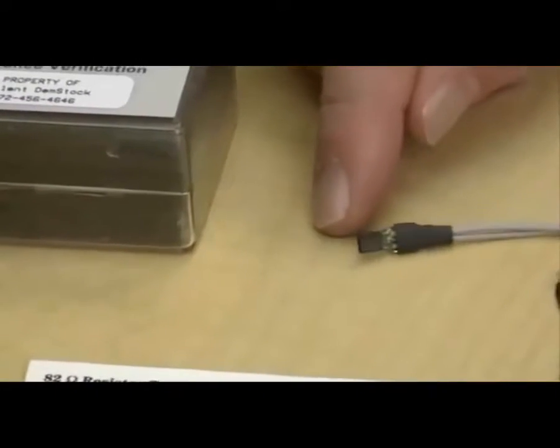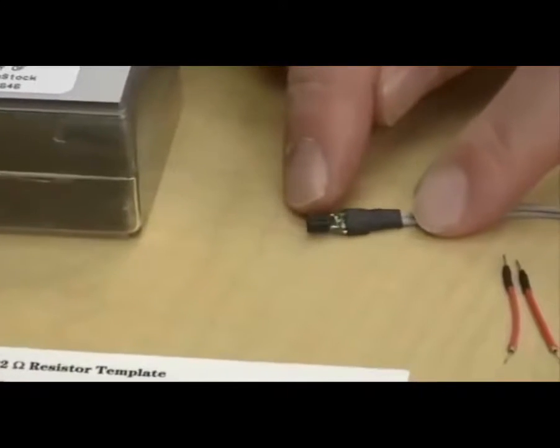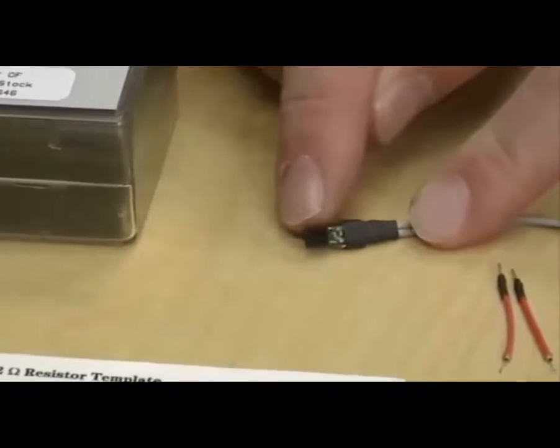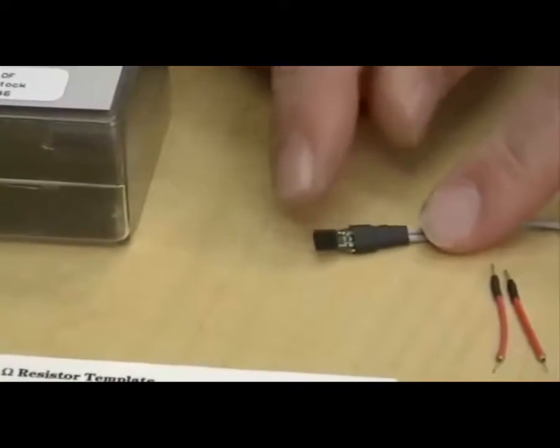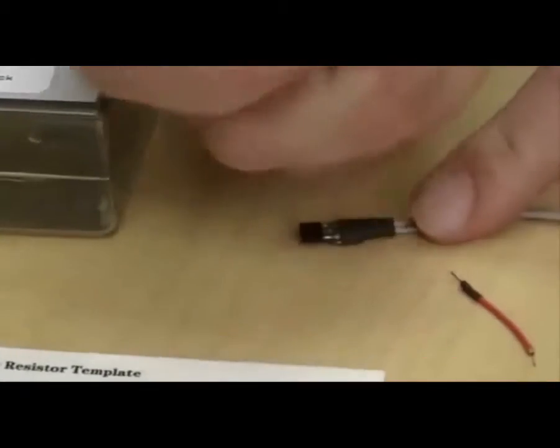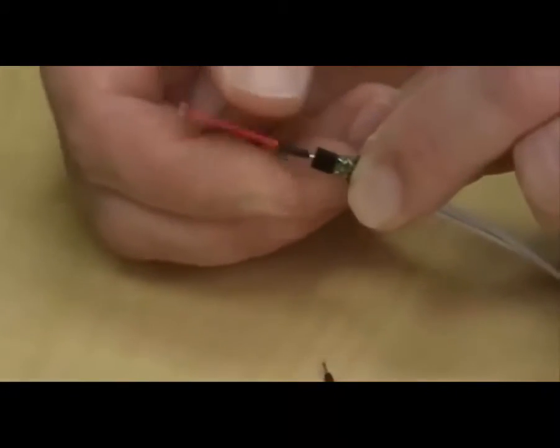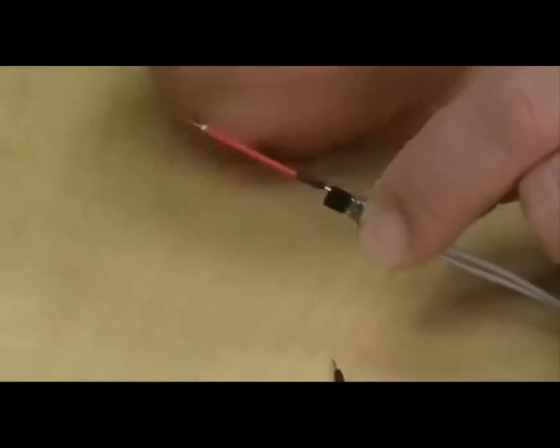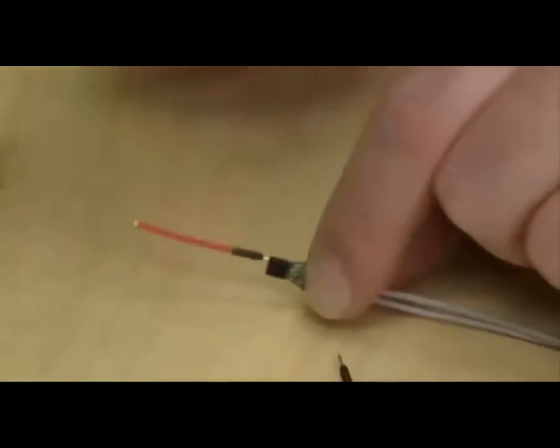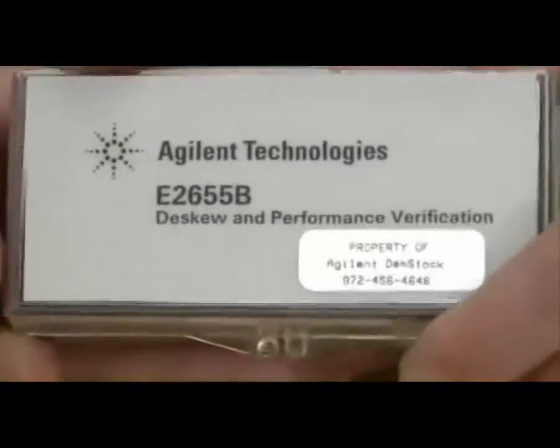To calibrate the E2678A or B socketed head, we have to actually put in the connections that we're going to use with our real life DUT. In some cases, we might use the damped wire accessories and we'll just insert them, basically like this, right into the left and right pins. And then we'll actually connect to the E2655 calibration fixture.